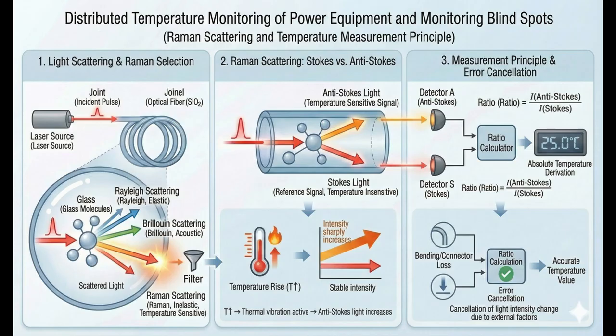The key to DTS temperature measurement is Raman scattering. When a laser pulse is launched into the fiber, scattered light returns. Among the Stokes and anti-Stokes components, the anti-Stokes signal is especially sensitive to temperature. The system calculates absolute temperature using the ratio of these two signals, reducing errors caused by optical loss or external disturbances. As a result, it provides stable temperature data even across long distances.